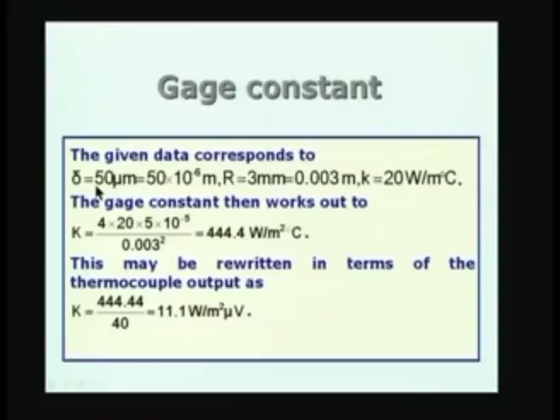You will notice that the gauge constant is in the units of the heat transfer coefficient. In fact, now I can rewrite this in terms of the thermocouple output, and you remember 1 degree Celsius corresponds to about 40 microvolts. So, instead of 1 degree Celsius, if I put 40 microvolts here, I will get 444 divided by 40, which is equal to 11.1 watts per square meter per microvolt. So, this is the performance index, or the gauge constant, for the foil type sensor with delta equal to 50 micrometers and R equal to 3 millimeters.